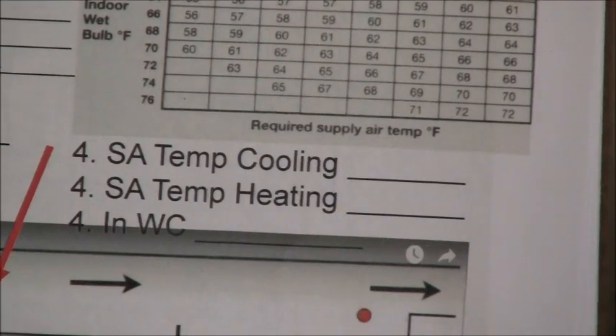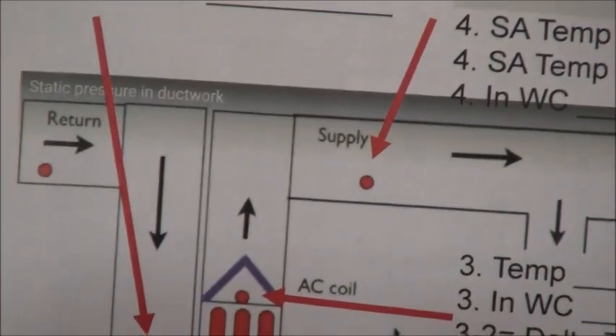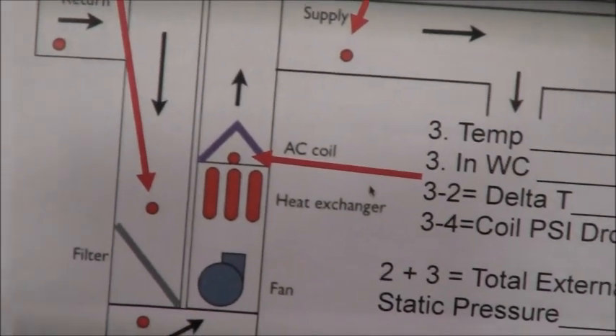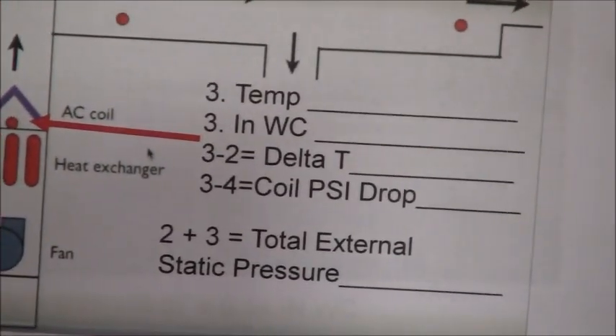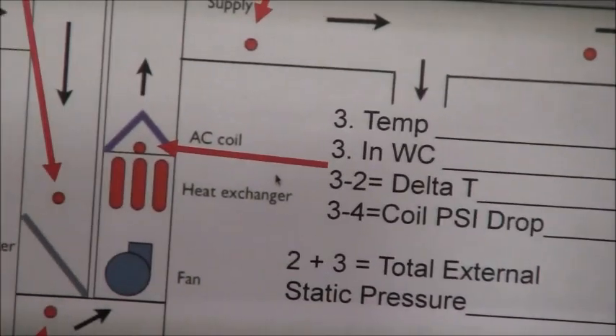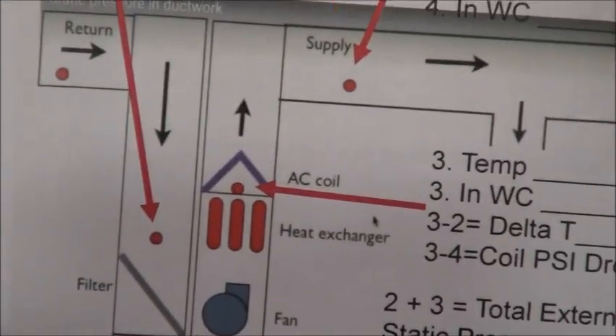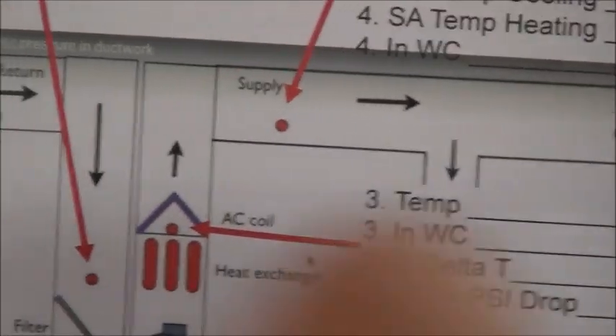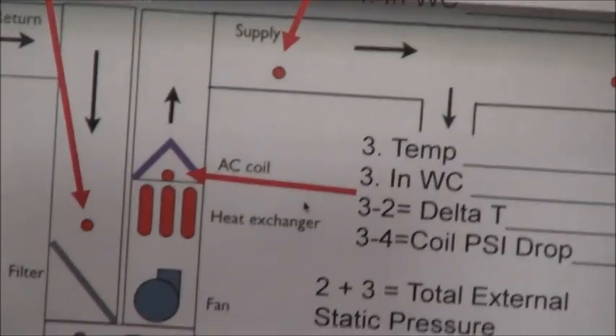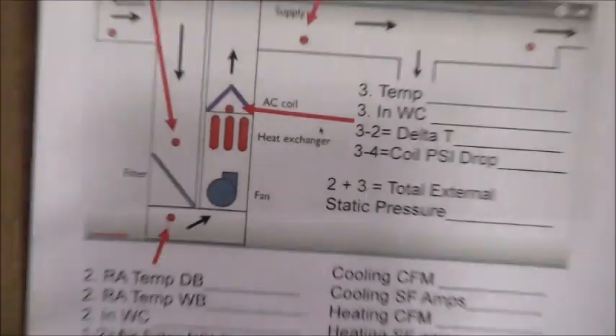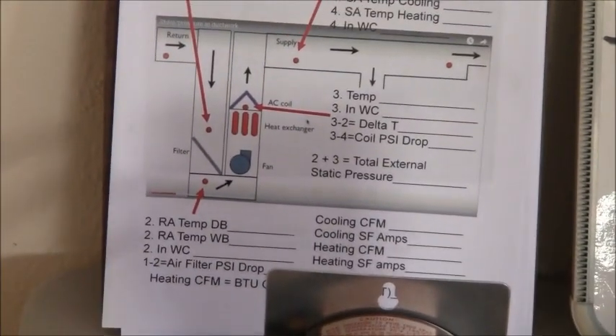We're going to get some temperature readings — supply air temperature for cooling and heating — and the inches of water column at sample point 4, which is after the AC coil. We're going to get the delta T, the temperature difference, which is point 3 minus point 2. We'll go through the whole thing and make sure you've got it 100%.